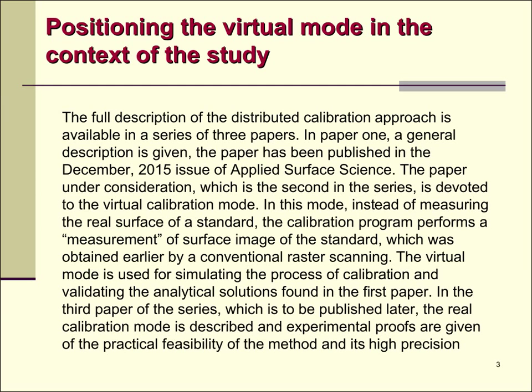The full description of the distributed calibration approach is available in a series of three papers. In the first paper, a general description is given, published in the December 2015 issue of Applied Surface Science. The paper under consideration, which is the second in the series, is devoted to the virtual calibration mode. In this mode, instead of measuring the real surface of a standard, the calibration program performs a measurement of a surface image of the standard obtained earlier by conventional raster scanning. The virtual mode is used for simulating the process of calibration and validating the analytical solutions found in the first paper. In the third paper of the series, which is to be published later, the real calibration mode is described and experimental proofs are given of the practical feasibility of the method and its high precision.